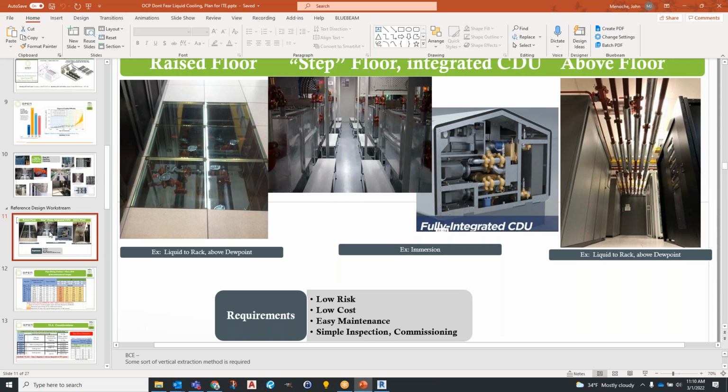From what I'm seeing in the design work we're doing, it's the front to back depth, the access clearances, and the height. And when I talk about the height, I think it's important to remember that we're talking about the full height of not just the enclosure, but the maintenance access as well. This is particularly important when we talk about vertically loaded immersion.